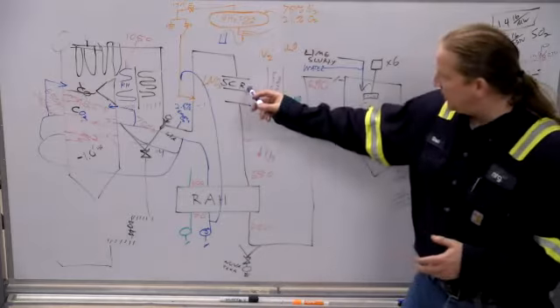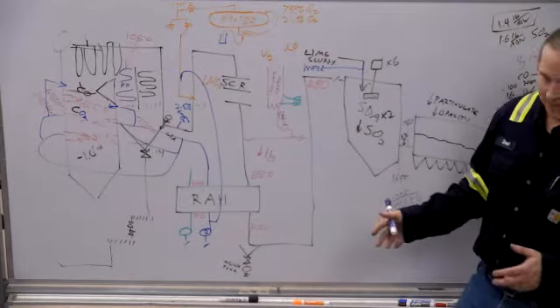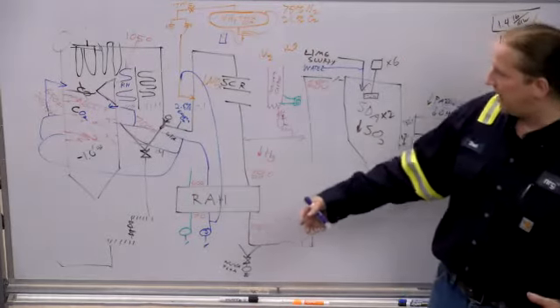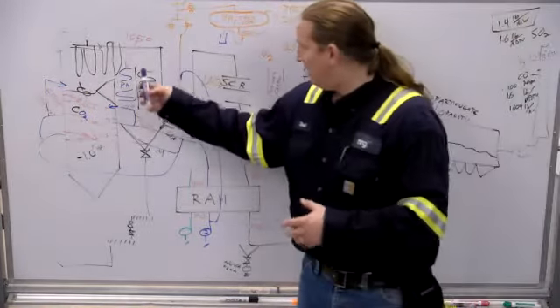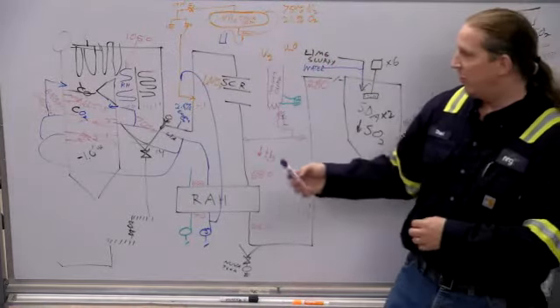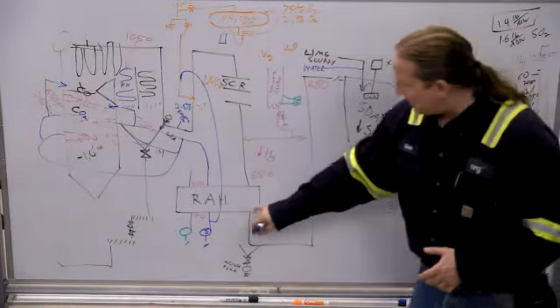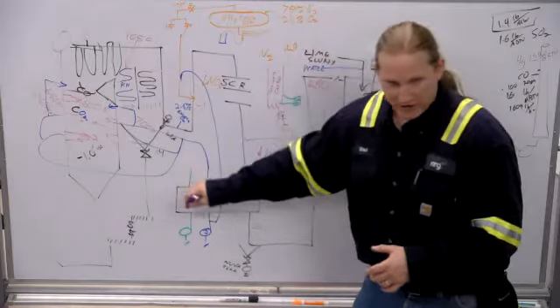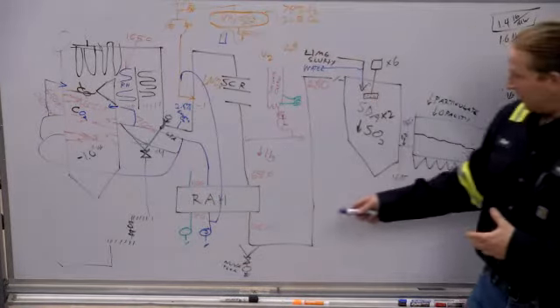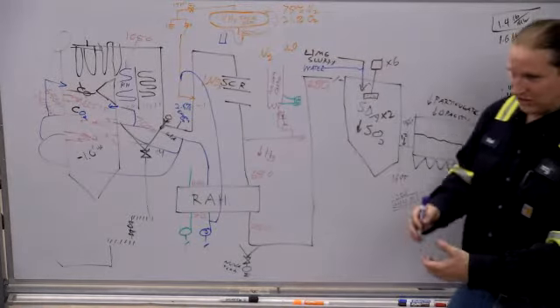One is the SCRs have been known to get clogged up. And when you get clogged up on the north side but not on the south side, that means more flue gas is going to go through the side that has least resistance. So you get more flue gas on the south side, so then the same amount of cooling air at the rotor air heater means that you're still hotter going out. And so that's one way that this split happens.